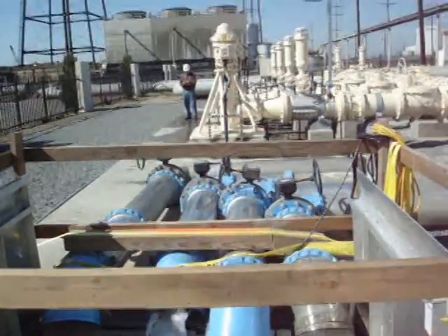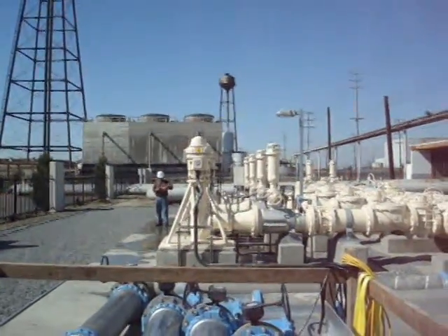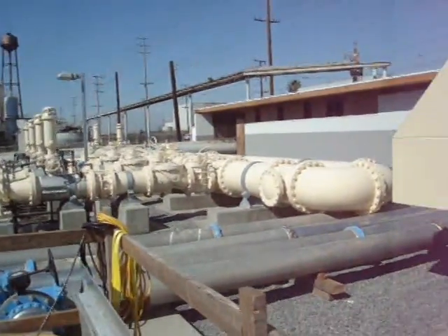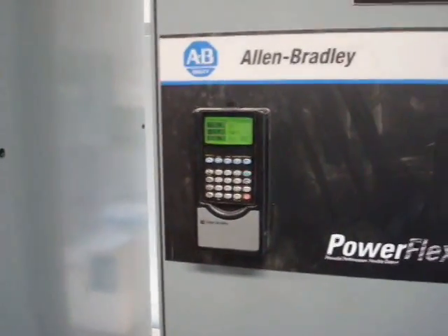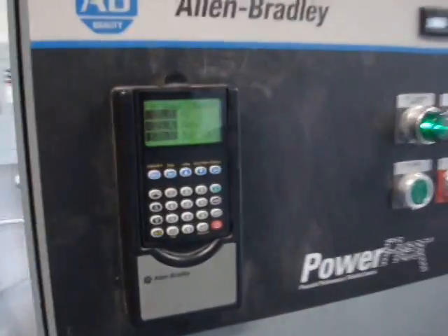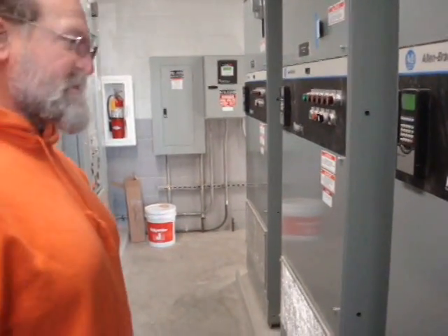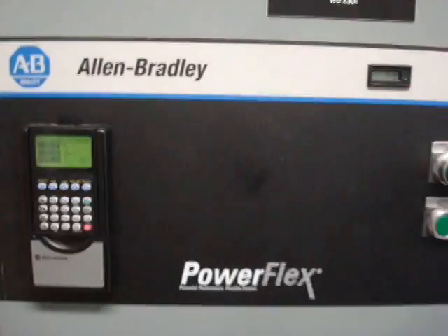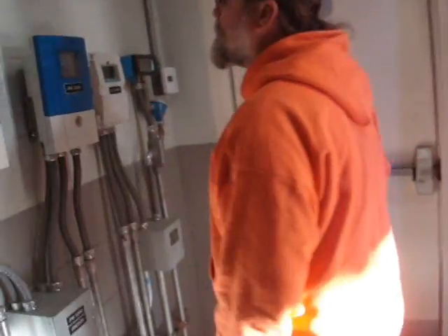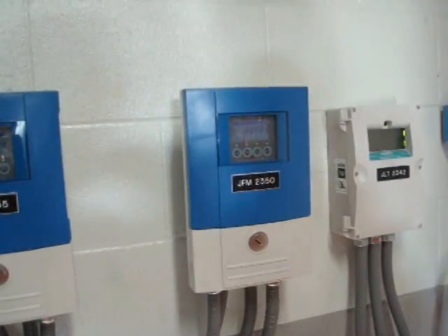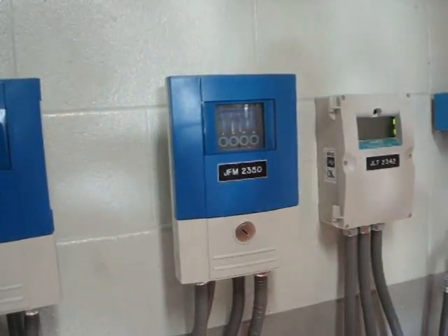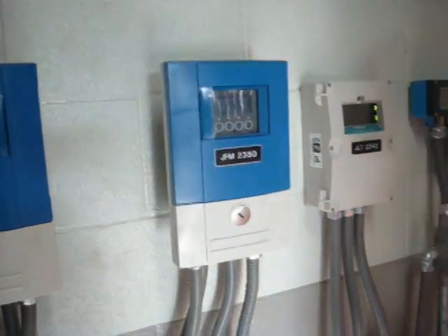Here's the actual flow output. 35 Hertz, 35 Hertz. And we're pumping what, 6,600 gallons per minute. Okay, and these are still at 30 Hertz. 30 Hertz for each of these. So I'll just let it run at that. And now it's running at 67, almost 6,700 or so. 66. Okay. I mean 67. All right.